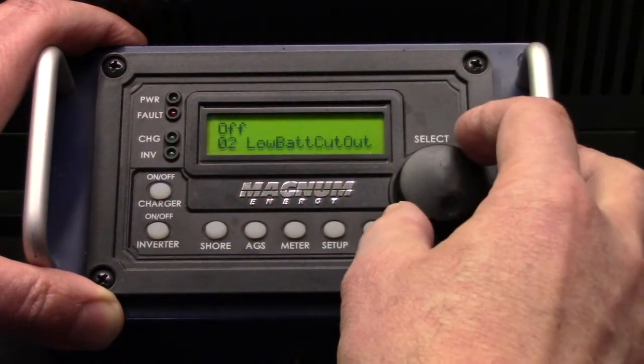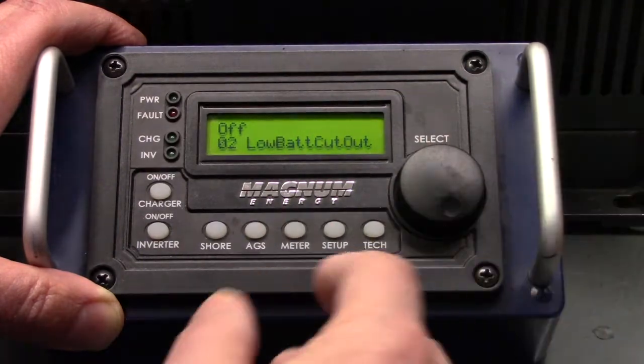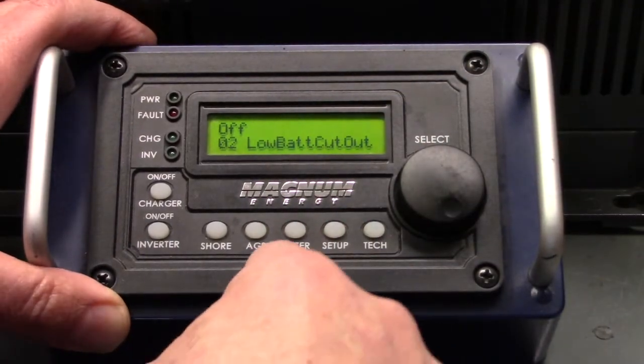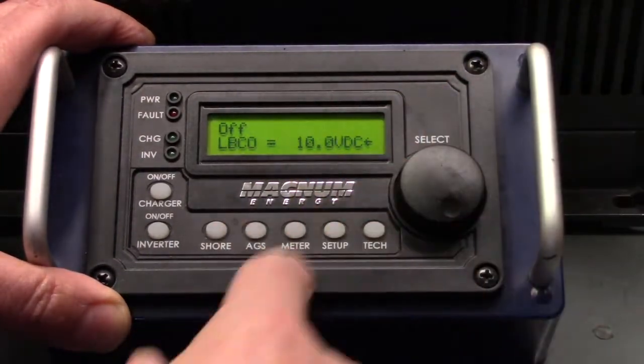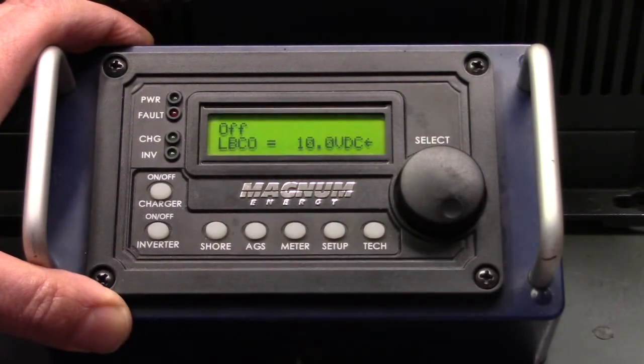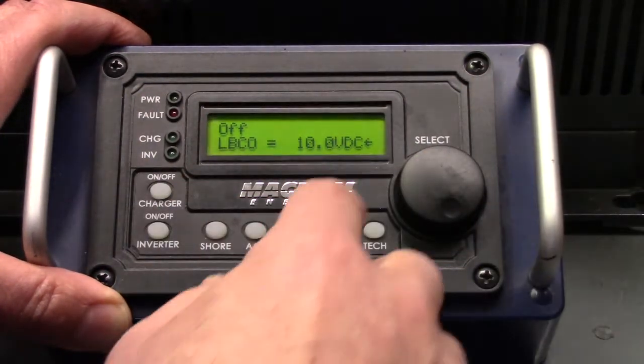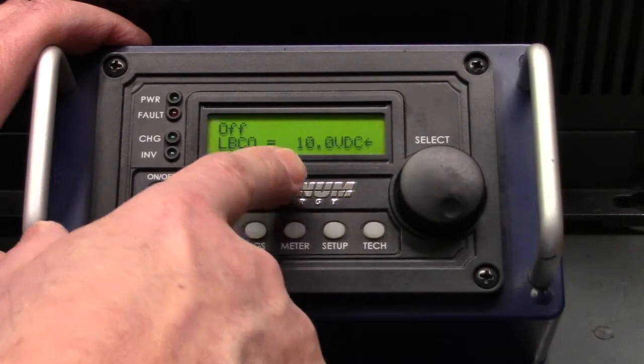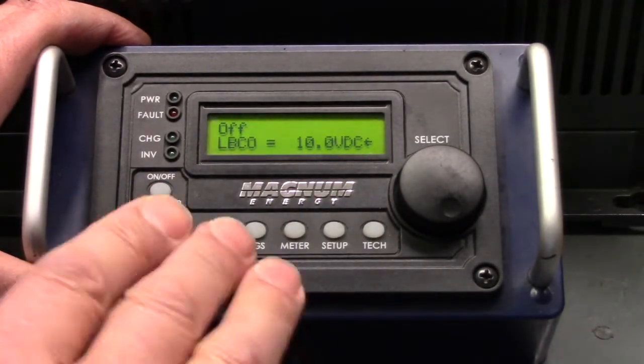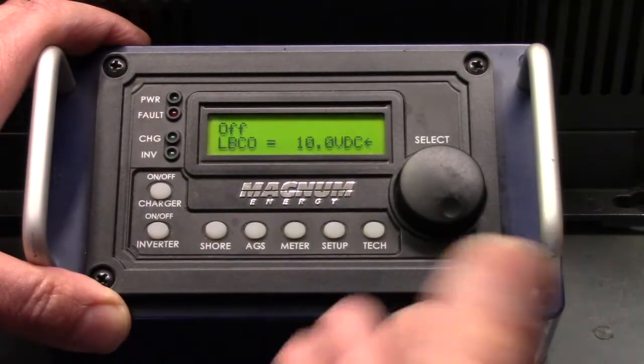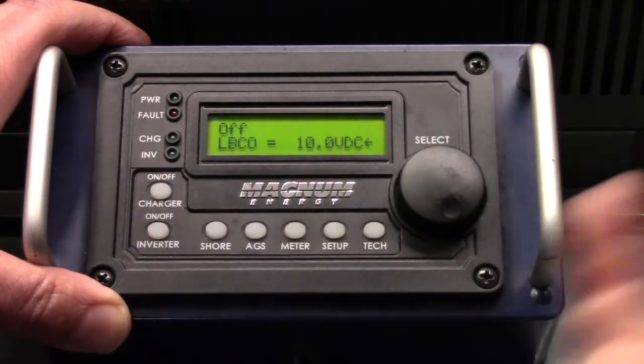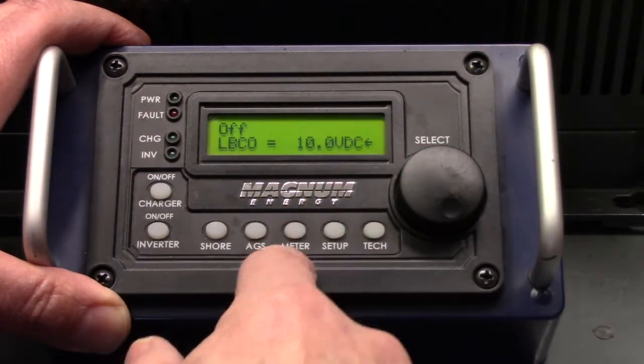After search watts, you have low battery cutout. The factory default for that is fine, which is 10 volts. If you want the batteries to shut down sooner, you can do that—it's just how low you'll let the batteries go before the inverter shuts off automatically. 10 volts is the factory setting, and that's fine for a 12 volt system.